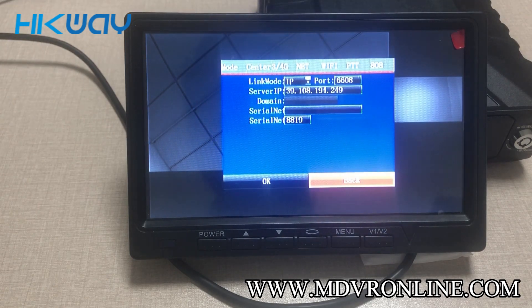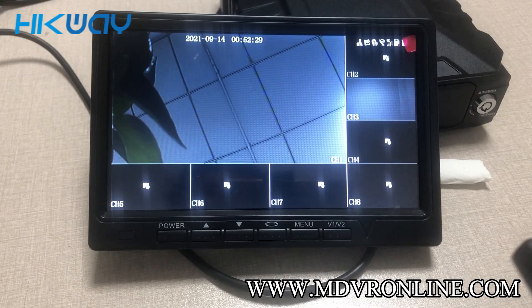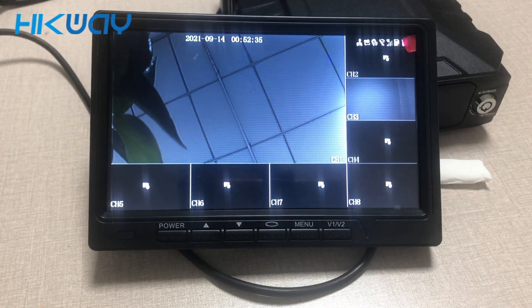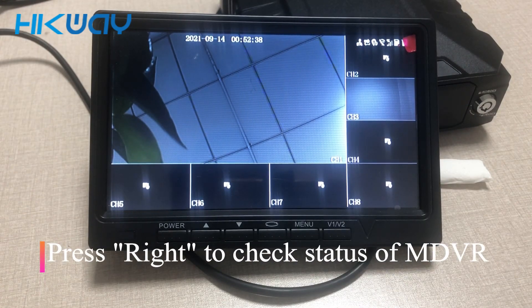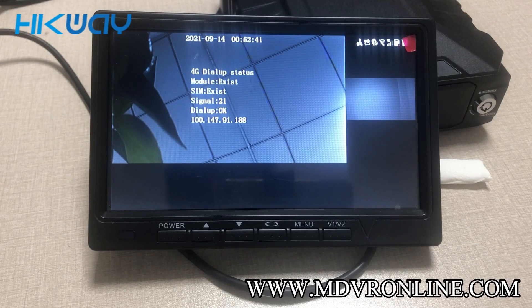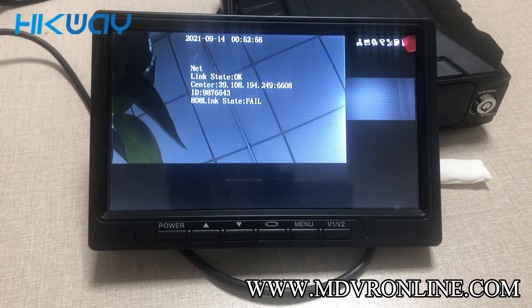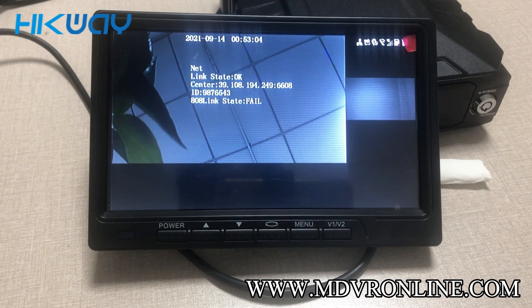Press okay, then let's press the right arrow on the remote control to see the status of the mobile DVR. You can see the 4G dial-up status — dial-up okay. Press right arrow and you can see other status. You can see the center server link status is okay, so that means the mobile DVR is on the platform now and you can check on the platform.